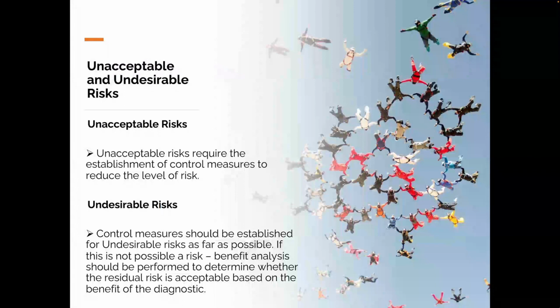There is an expectation within the IVDR regulations that you should continuously reduce risk. So even if you are in the acceptable zone, you are actually expected to at least consider driving that risk down even lower. So there is an expectation within the IVDR and the MDR regulations that just because you land in a green zone, if you can do something and you can reduce risk further, you really should consider that.